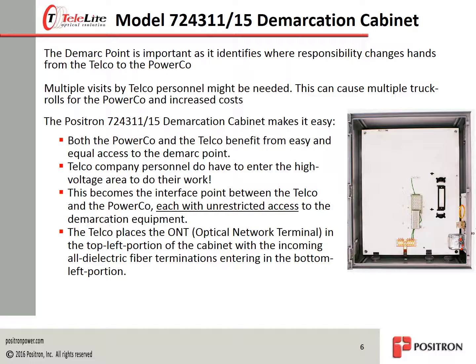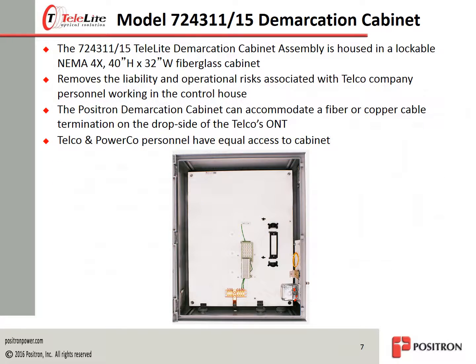The telephone company can place their ONT, or optical network terminal, in the upper left portion of the demarc cabinet. The power company places their terminating copper or fiber cable in the upper right-hand portion of the demarc cabinet. The whole of the left-hand side of the white-painted backboard of the demarc cabinet is reserved for the telephone company's optical termination equipment. The copper output of the optical network termination can be punched onto the 25-pair 66-type solid-state protector block located in the lower center of the cabinet.